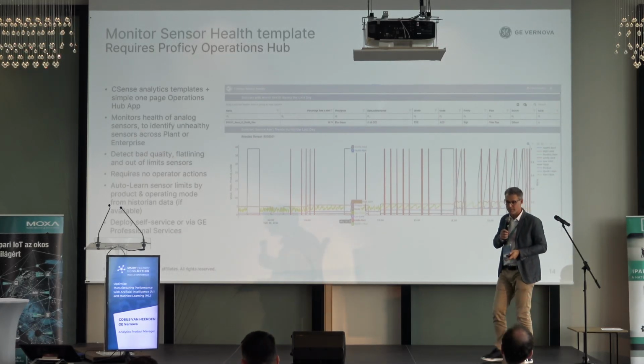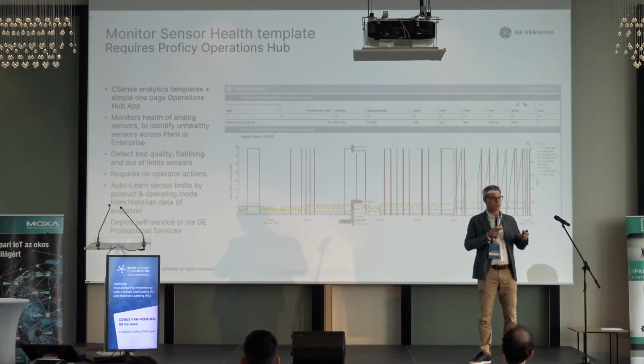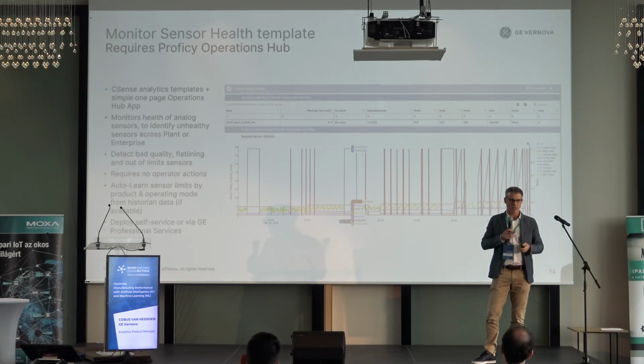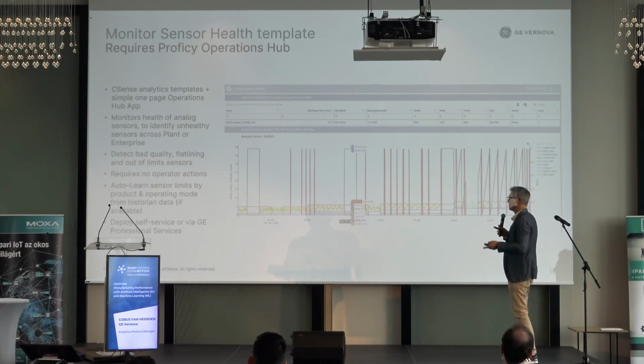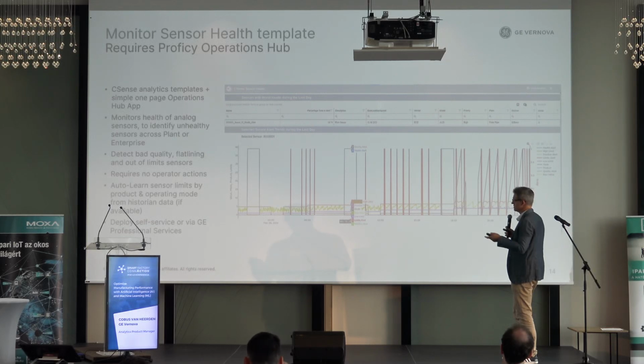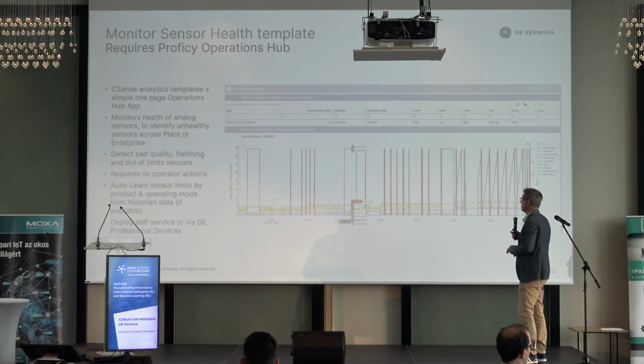Sensor health. So typically, SCADAs are connected to sensors and monitor them, and sensors can stop working. Sometimes they produce bad quality data, or they go out of limits or calibration. And there's a simple template to monitor the health of sensors. Is it producing bad quality data? Is it just flatlining or not changing anymore? Is it outside normal limits?